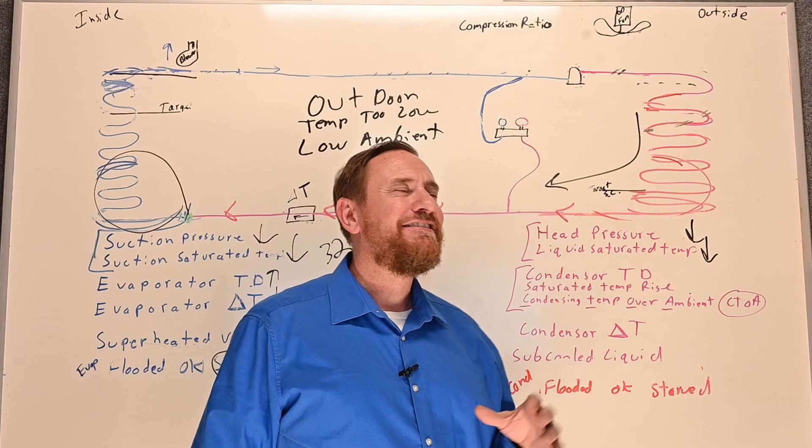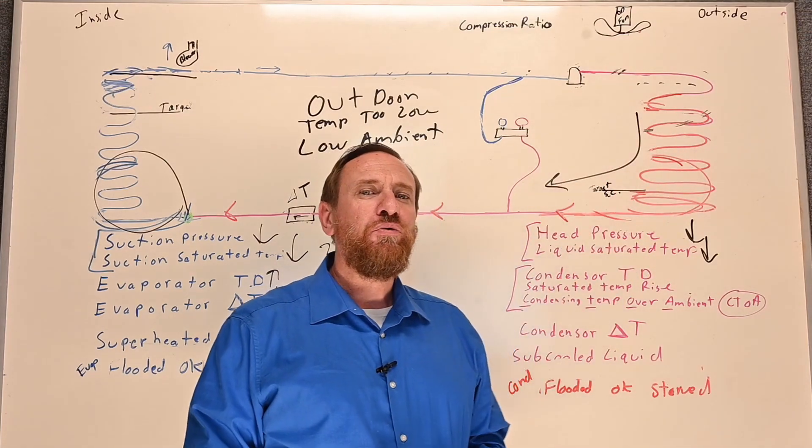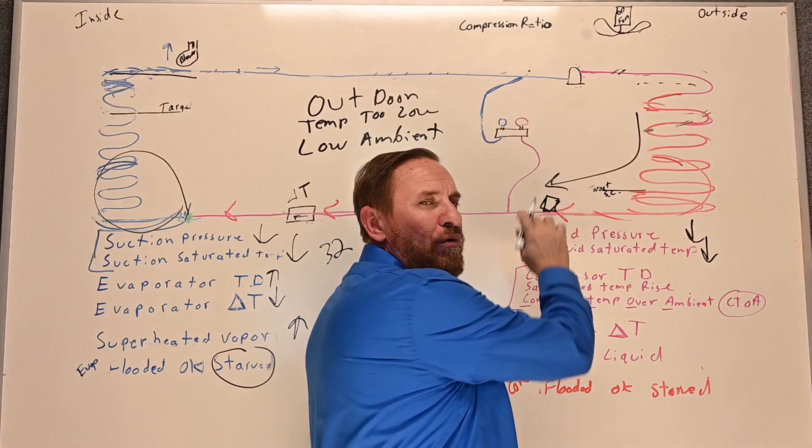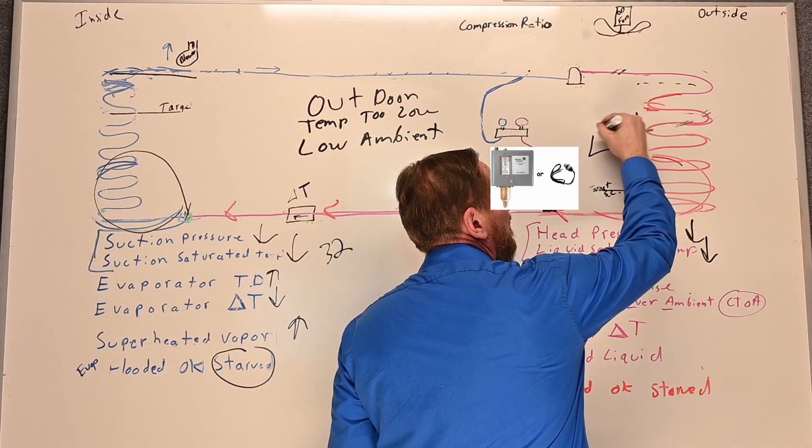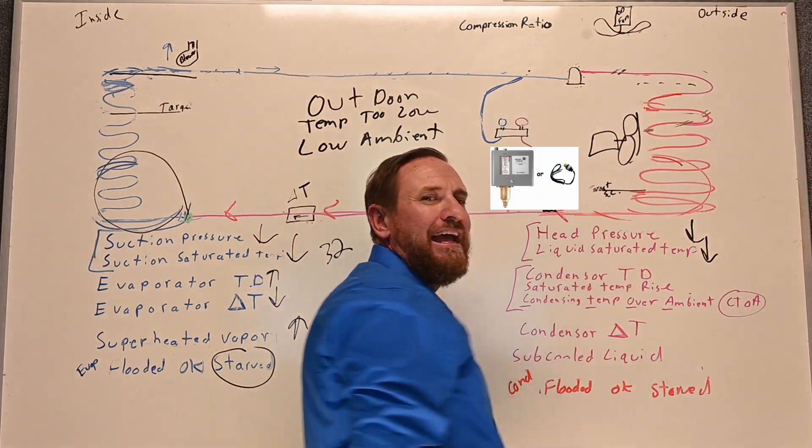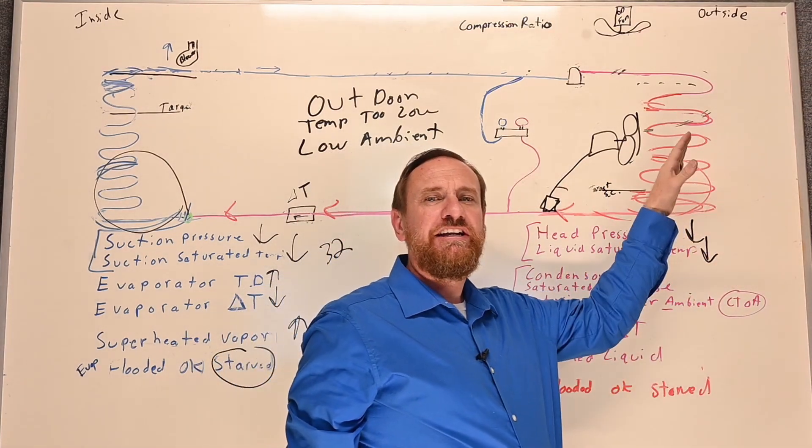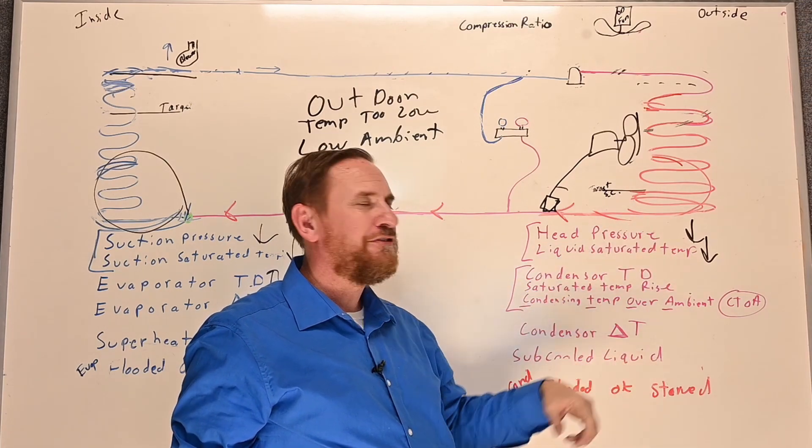So a low ambient kit simply means we need to increase the pressure. So I need to get more pressure right here. So one of the easy ways that we do is we put a pressure switch right here on the liquid side. And that pressure switch goes to our fan motor right here. And the pressure switch simply controls this fan motor. So as the temperature outside goes down, we know that our head pressure goes down and all this other stuff starts changing as well.